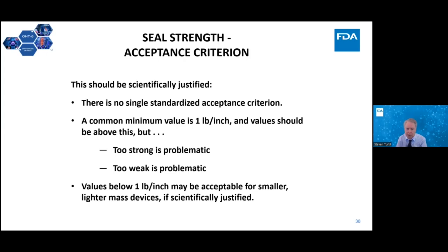It's not FDA recognized. And as long as I've been doing this, my first standards meeting goes back almost 20 years ago, and I approached the co-chair and I said, what is an acceptance criteria for seal strength? And he says, we've never been able to get consensus opinion on that. A very common value is 1 pound per inch. It's very common. And we see values all the time between 1.5 and 2 pounds per inch.